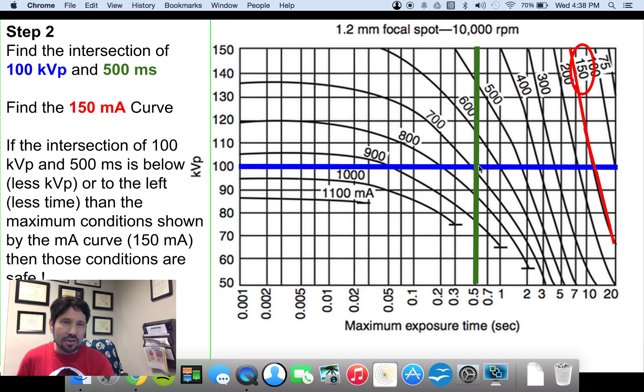So my green line shows 0.5 seconds. My blue line shows 100 kVp. And so this intersection is the conditions that we're going to compare with the 150 mA curve. So this chart is telling me that anywhere on this red curve is the maximum kVp time combination that I can do at 150 mA. So I can do 70 kVp for almost 20 seconds, maybe 15 seconds. Or I can do a higher kVp like 140 kVp, but I can only do that for like seven seconds. So if my intersection point of the conditions in the question is to the left of, so it's a lower time or below a lower kVp, then they're safe.